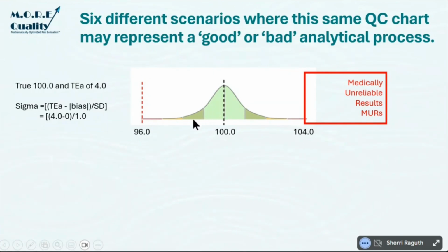If it fell down here, it would be about -1.5 on the QC chart. If it fell out here, it would be +3 on the QC chart. So the QC chart is this curve turned on its head, or turned on its side, rather. So the same distribution is here and here. Your QC chart only typically shows you the measured mean plus or minus 4 standard deviations, which by coincidence is exactly what this one shows you.